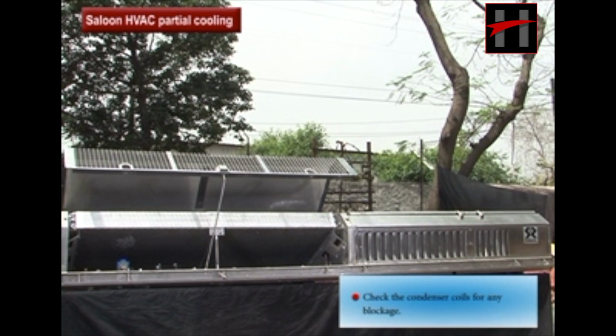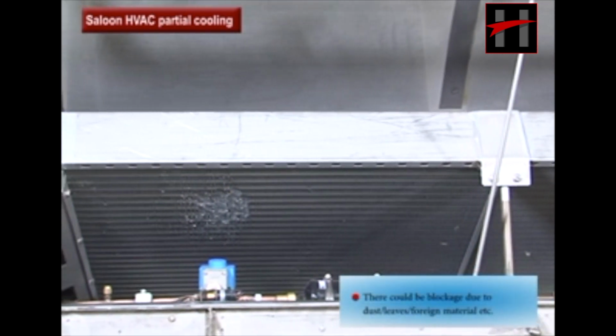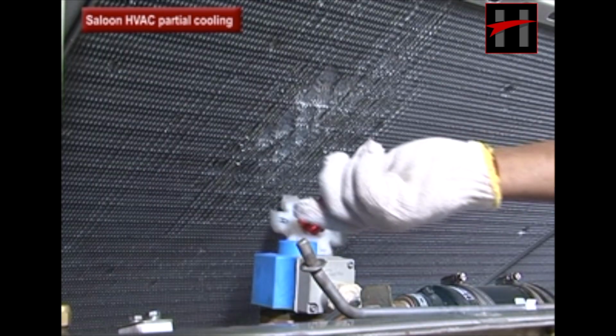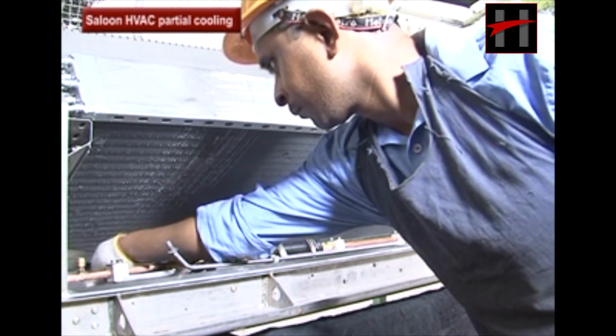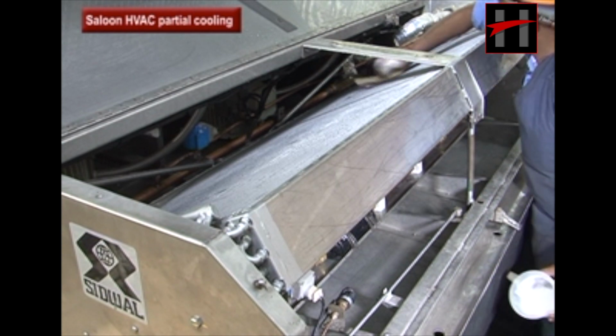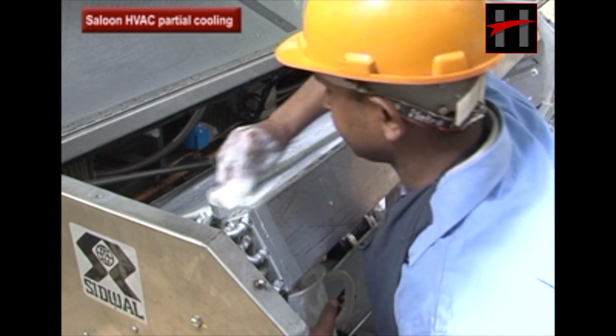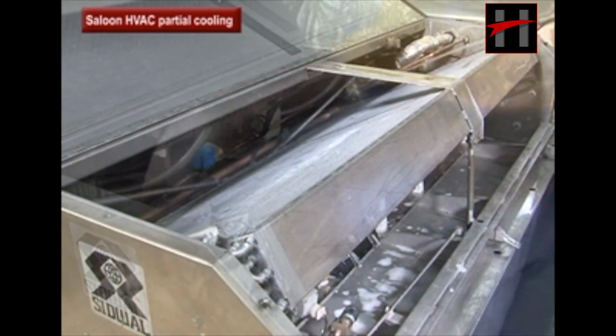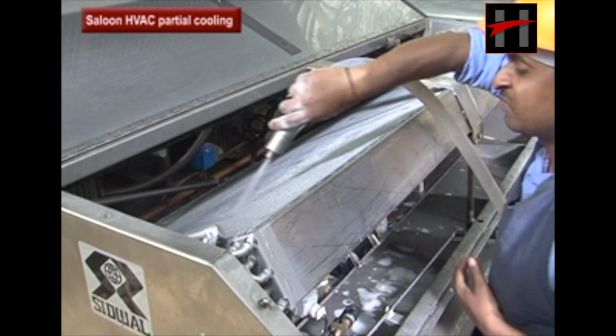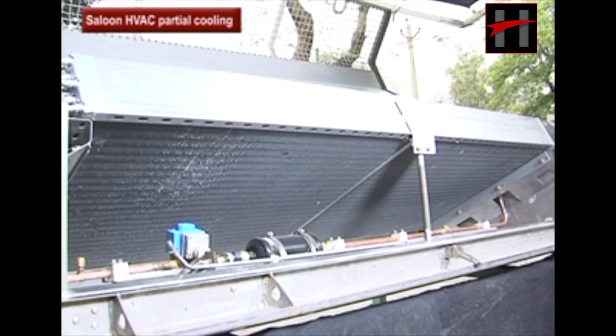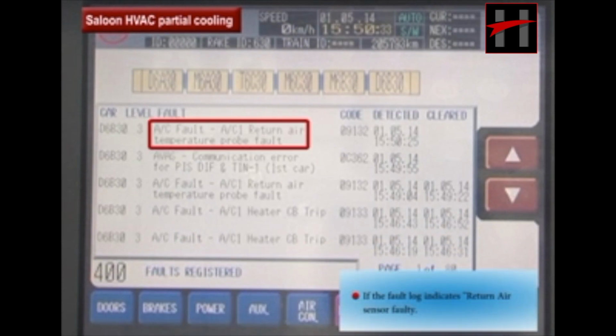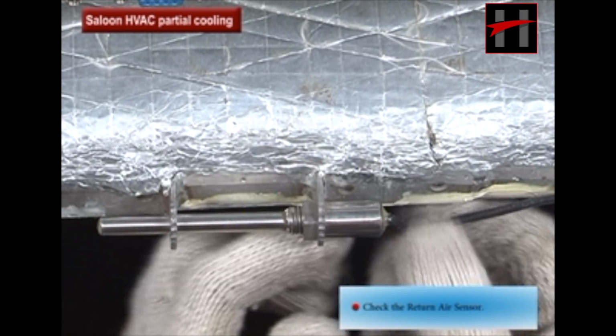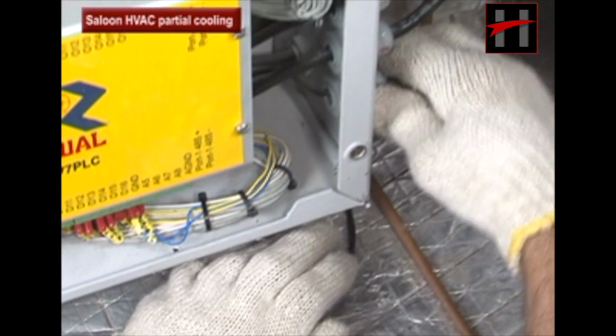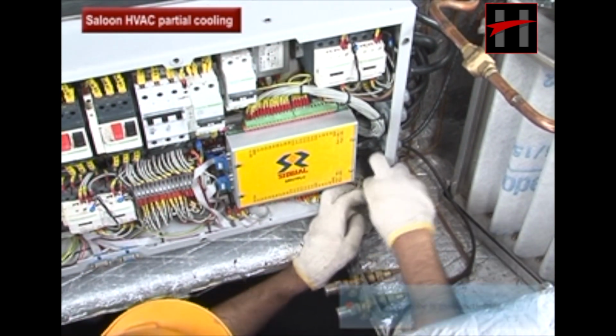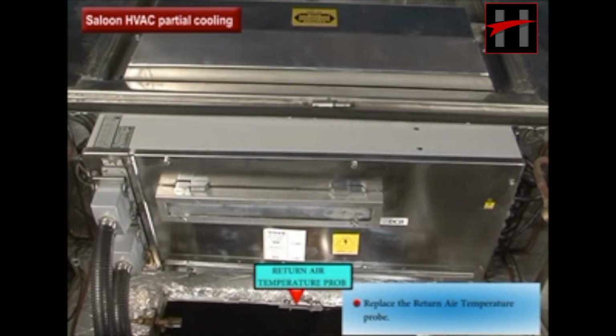Check the condenser coils for any blockage. There could be blockage due to dust, leaves, foreign material, etc. Clean the condenser coil. If the fault log indicates return air sensor faulty, check the return air sensor. If the return air sensor probe is malfunctioning, replace the return air temperature probe.